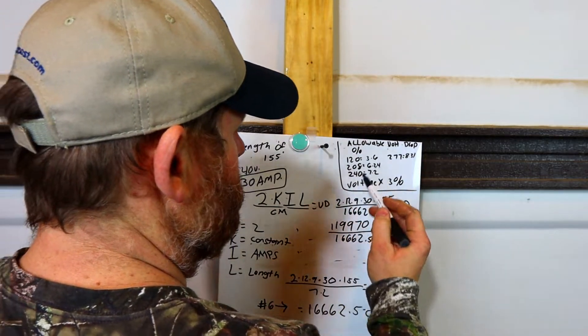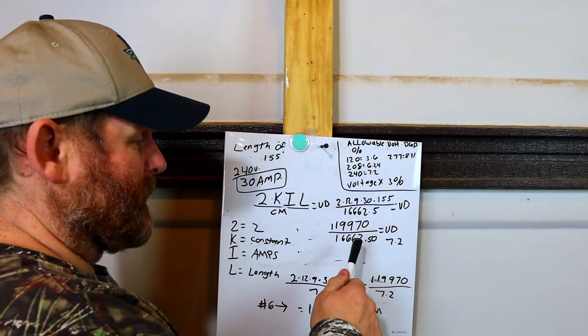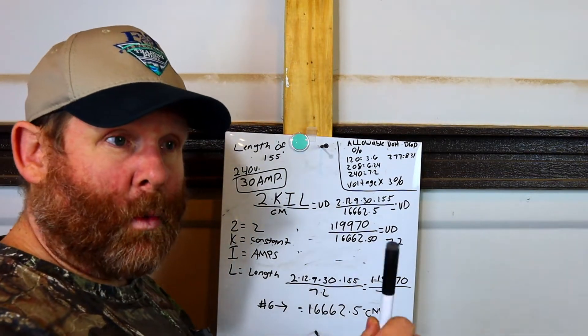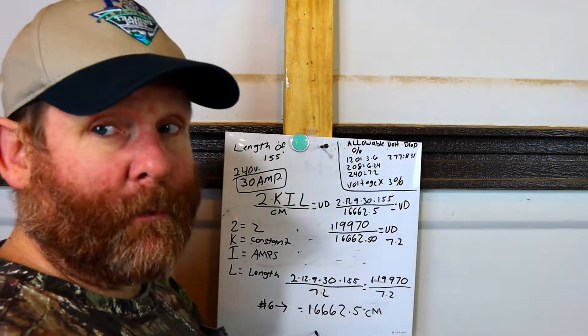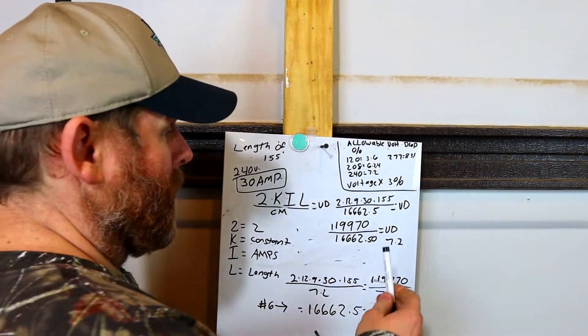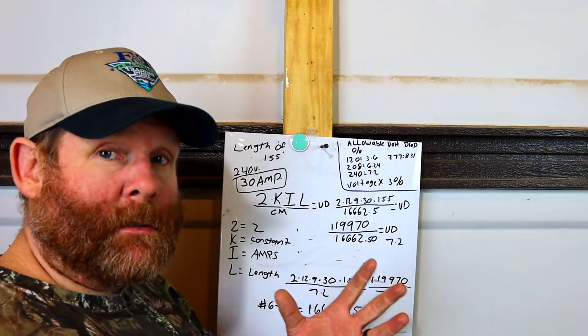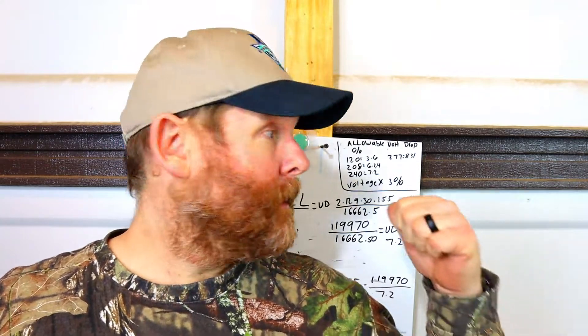So now we know that these numbers equal a 7.2 volt voltage drop, which we know we are 100% okay with. Now technically, if you remember, the actual circular mils jumped up to 26,240 for the #6 wire — that's a big jump. So technically your voltage drop will actually be less than 7.2 because the wire is a little bit bigger. But this is how you figure it out. These calculations are important if you are wiring anything — campers, gazebos, sheds, garages — anything.